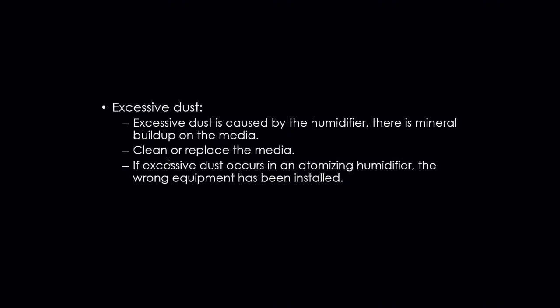Excessive dust is caused by the humidifier. There is mineral buildup in the media. All of those things can clog up a humidifier's sprayers and break the components in there. Okay, we have to always clean and replace the media on a humidifier. Okay, if excessive dust occurs in an atomizing humidifier, the wrong equipment has been installed.